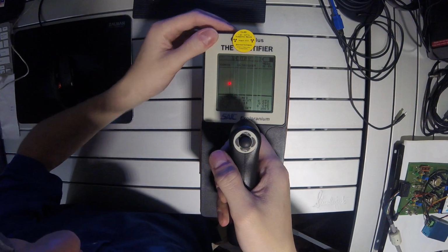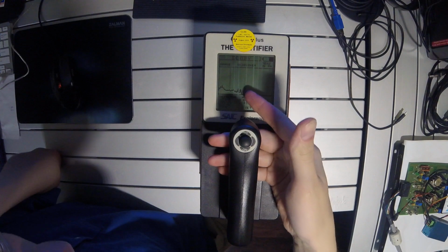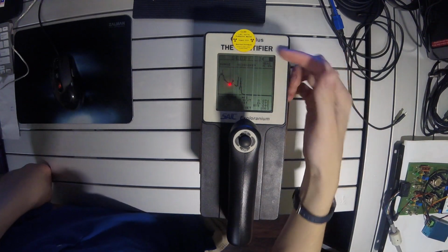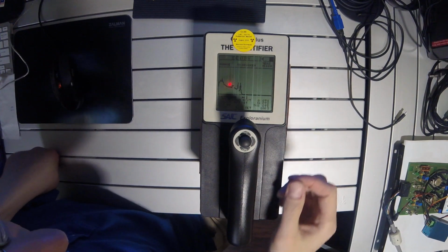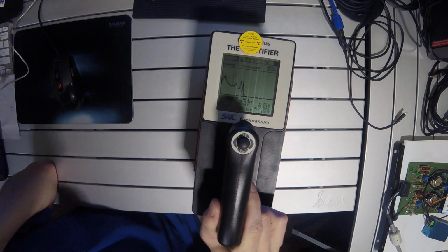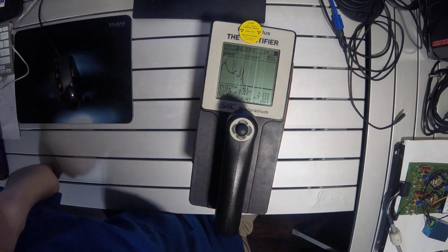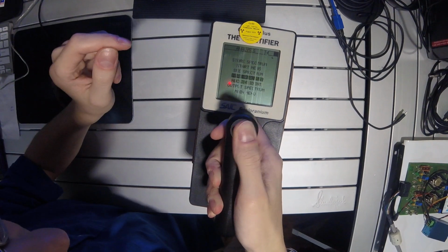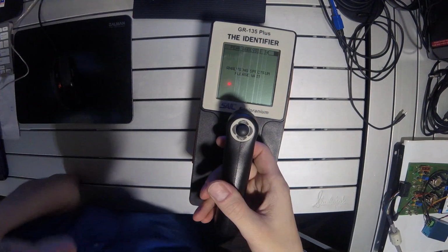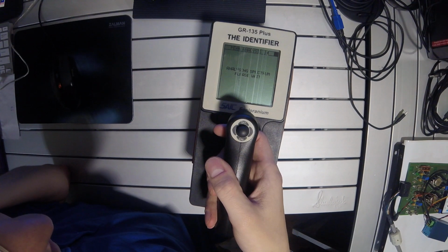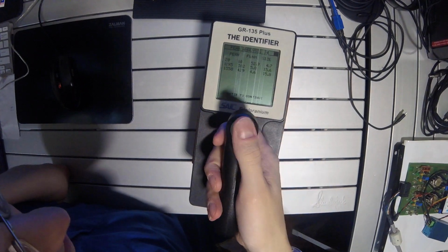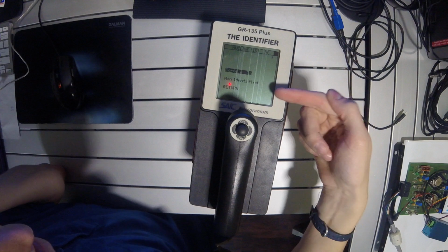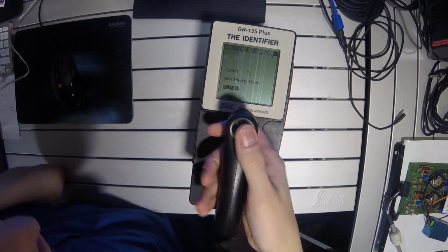this time with a 1 microcurie cobalt-60 source. So you see the cobalt-60 spectrum starting to form. And since this is a weaker source, we'll give it some more time to accumulate. Okay, that should be sufficient. So, canceling that acquisition, and peak analysis, so we'll search for peaks. It's analyzing spectrum, please wait. And there are the cobalt-60 peaks. So, nuclide identify, search in progress, and there it has cobalt-60. And then it also has some more non-identified background.